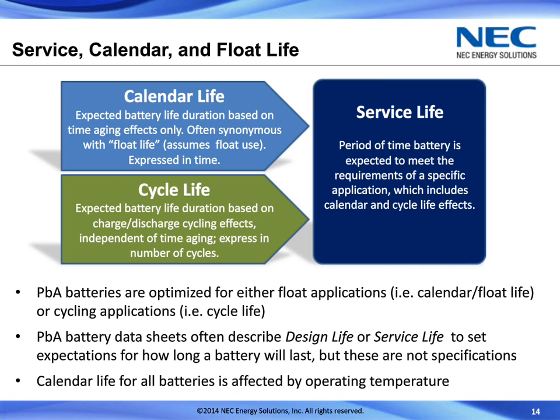If a battery is being used in a pure backup situation, where it's just left on a float voltage to keep the battery topped up with charge, and it's only going to be discharged when there's some type of event that the battery is there for, then the real life that matters is what we call the float life or calendar life. The other factor that comes into this is what we call the cycle life, and this is the number of times we can discharge the battery and charge the battery before the capacity of that battery is kind of used up, before it essentially wears out.